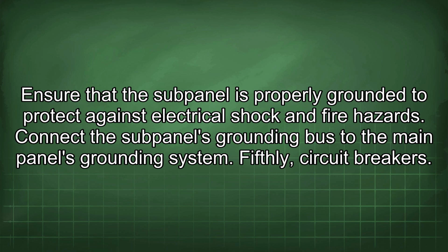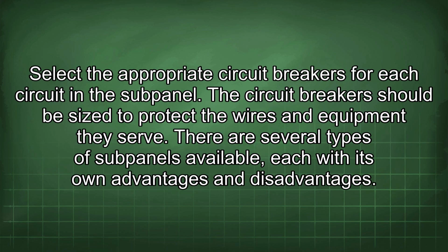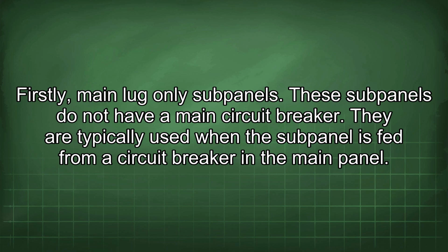Fifthly, circuit breakers. Select the appropriate circuit breakers for each circuit in this subpanel. The circuit breakers should be sized to protect the wires and equipment they serve. There are several types of subpanels available, each with its own advantages and disadvantages. Firstly, main lug-only subpanels. These subpanels do not have a main circuit breaker. They are typically used when the subpanel is fed from a circuit breaker in the main panel.